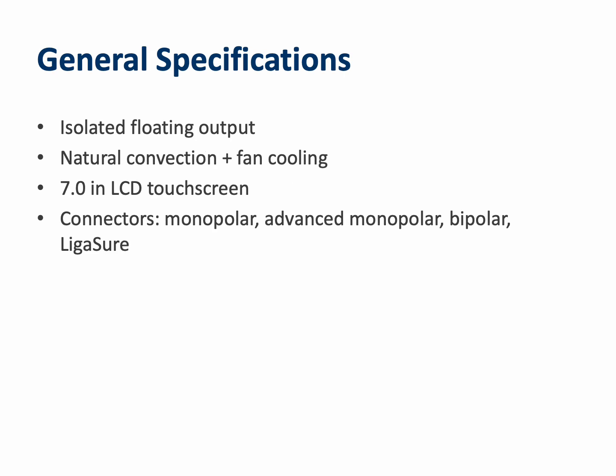The FT10 generator is built with reliability and safety in mind. Its output is isolated and floating relative to ground, which helps reduce electrical risks. Cooling is achieved with a combination of natural convection and active fans to prevent overheating during long surgical cases. The front interface is dominated by a 7-inch touchscreen, which provides a modern and intuitive control surface. Connector options support a wide range of energy modalities, including standard monopolar, advanced monopolar, bipolar, and LigaSure technology, making the FT10 versatile for multiple surgical specialties.